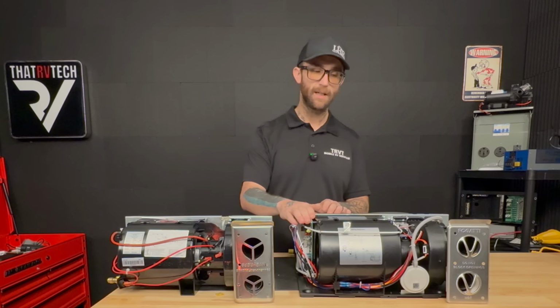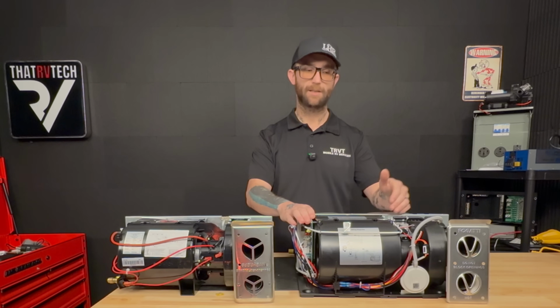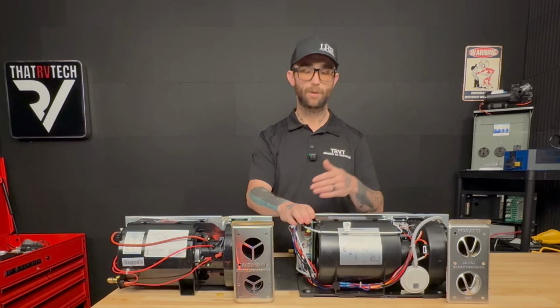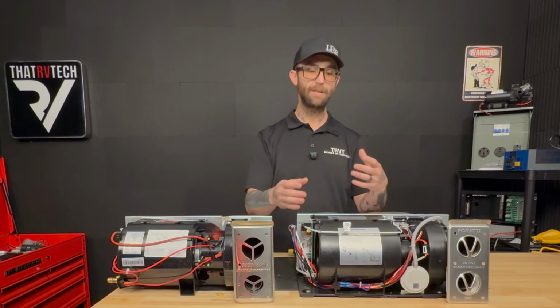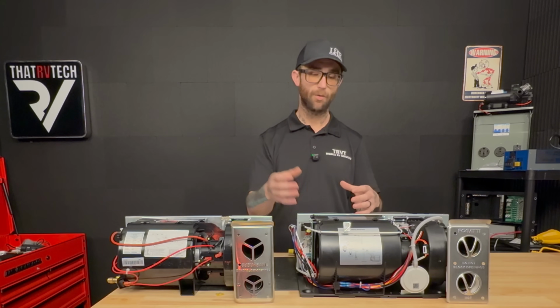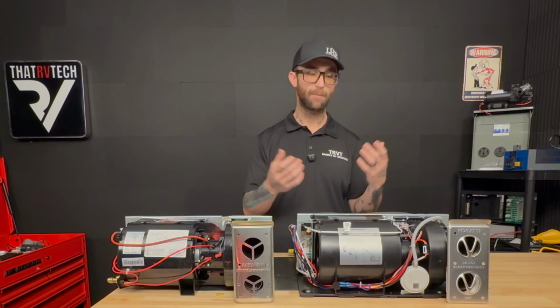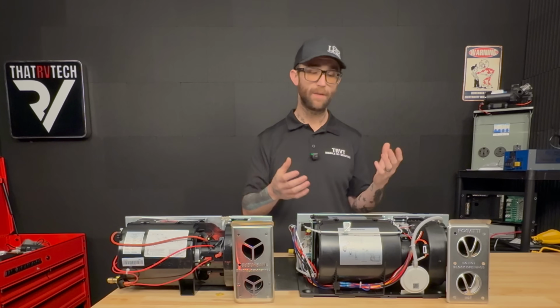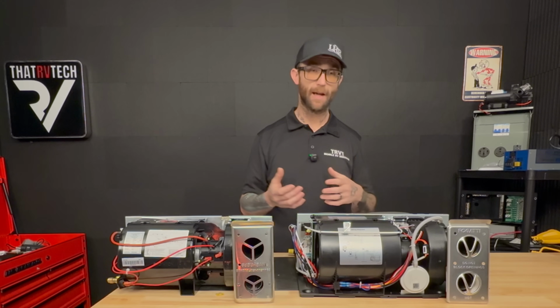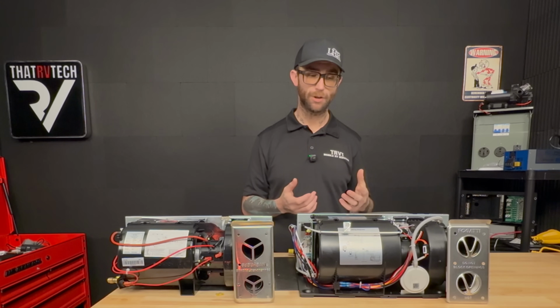The control board on this one, since each individual thing -- the gas valve, the pressure switch, the over limit switch, the blower motor -- every single device has its own input to the board, it's actually getting feedback on each individual device. So when this thing gives you error codes, it's actually guiding you closer to the true issue.